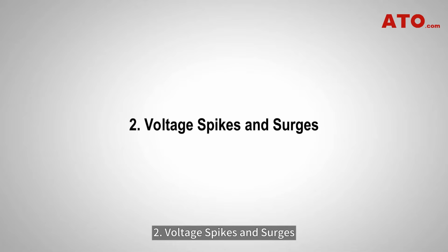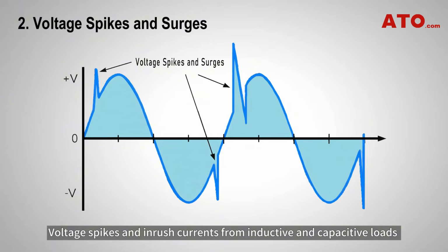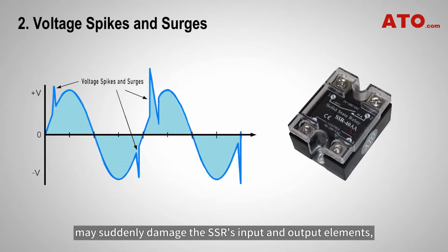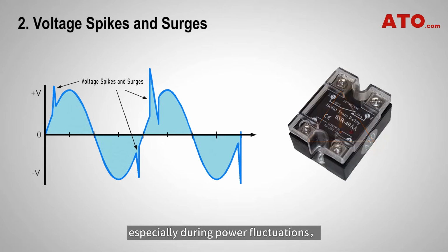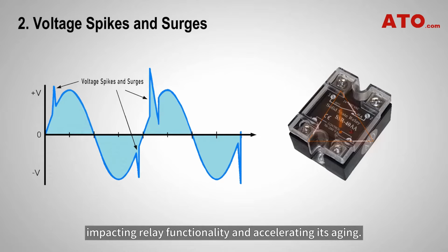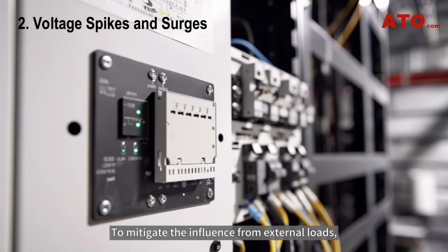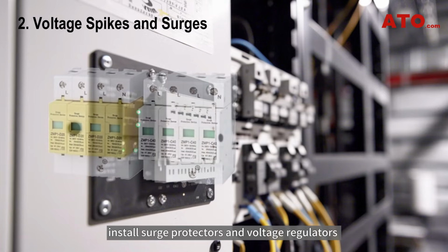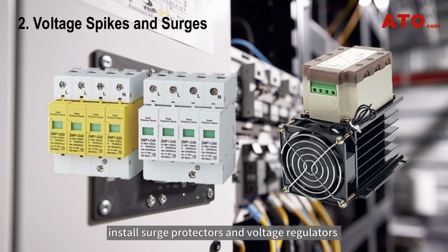Number 2. Voltage spikes and surges. Voltage spikes and inrush currents from inductive and capacitive loads may suddenly damage the SSR's input and output elements, especially during power fluctuations, impacting relay functionality and accelerating its aging. To mitigate the influence from external loads, install surge protectors and voltage regulators to protect relays from sudden voltage changes.